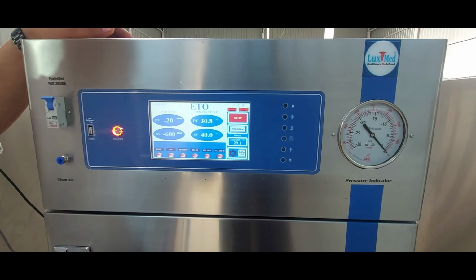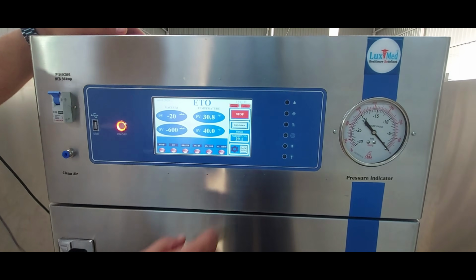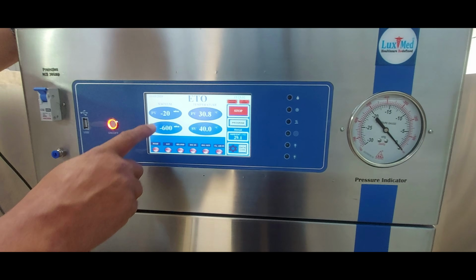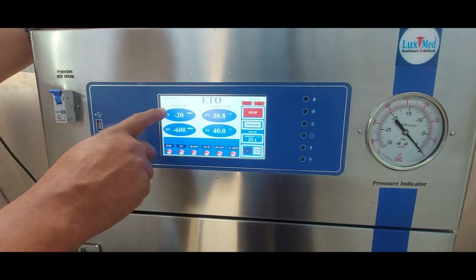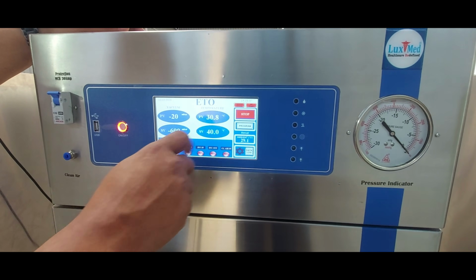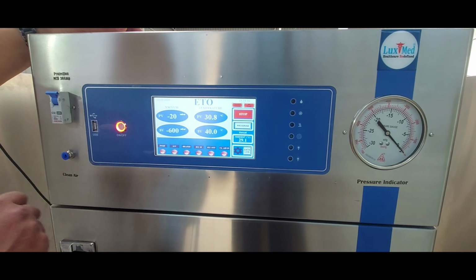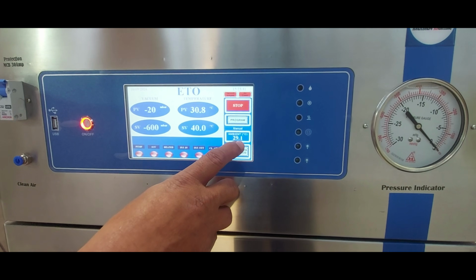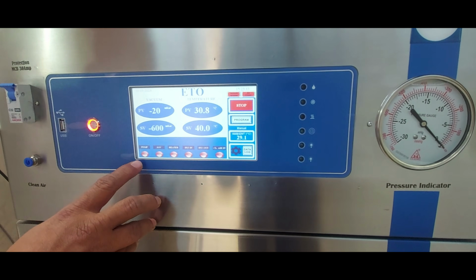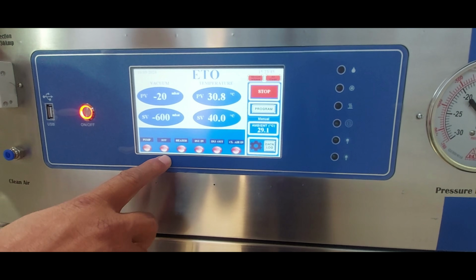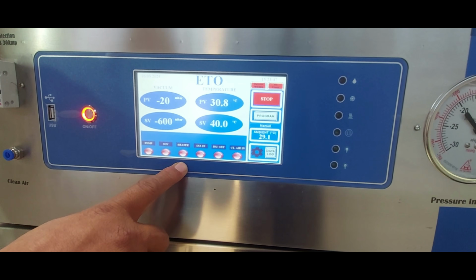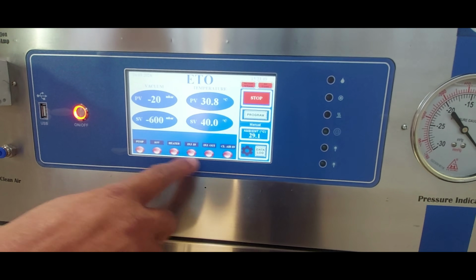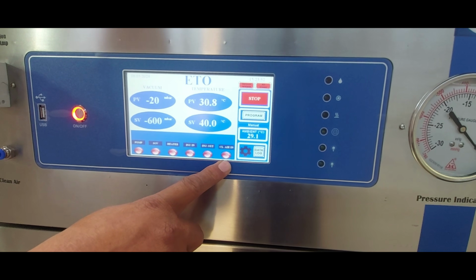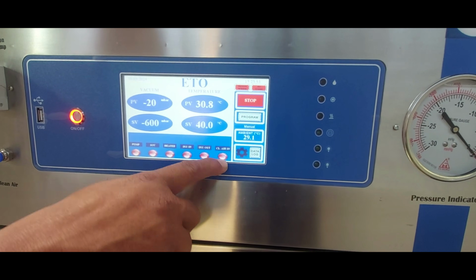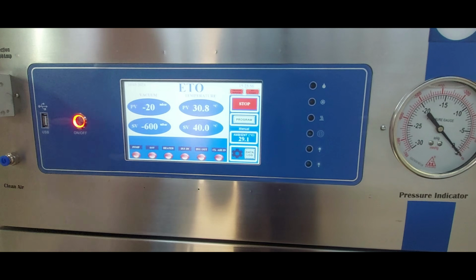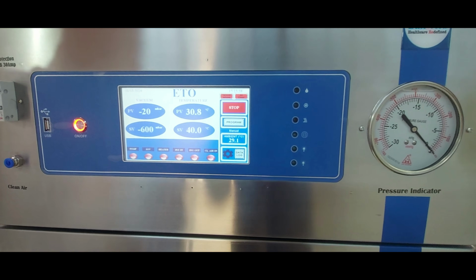Key considerations. Temperature. ETO sterilization is a low-temperature process, making it suitable for materials that cannot withstand high temperatures. Safety. ETO is toxic and flammable, requiring careful handling and monitoring. Validation. Rigorous validation is required to ensure the process consistently achieves sterilization and meets regulatory requirements. Aeration time. The time required for aeration can vary depending on the size, density, and material of the items being sterilized.